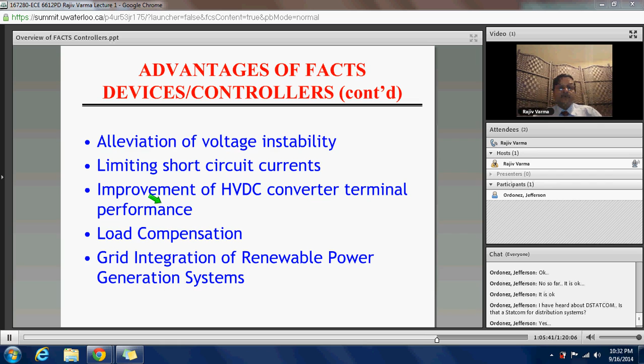So what are the compensators that we have with us? Our compensators are synchronous condensers. These are the age-old compensators. They are synchronous machines operated in motor mode, so they become like synchronous motors. Motors are typically meant to supply loads, but these motors operate on no load.